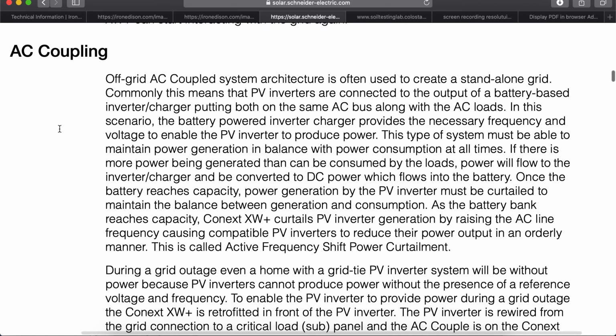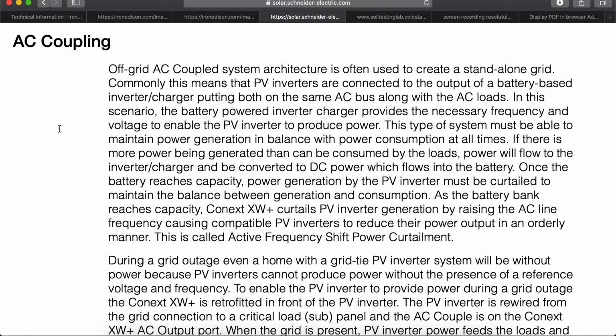Basically, when the grid drops off and somebody's out there wrenching on the wires, we just don't want to start selling power back, nor do we want to put AC output power back onto the grid. You don't want to power up your neighbors, and you don't want to power up the grid with your battery system. So that anti-islanding is a very important feature not to be engineered around.